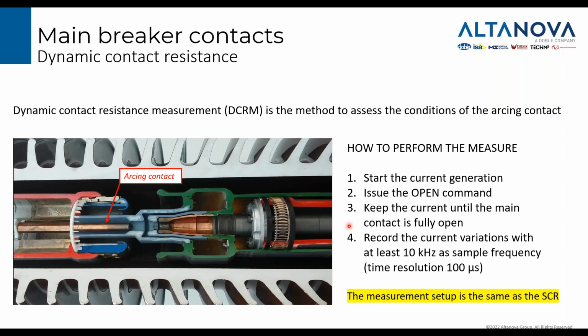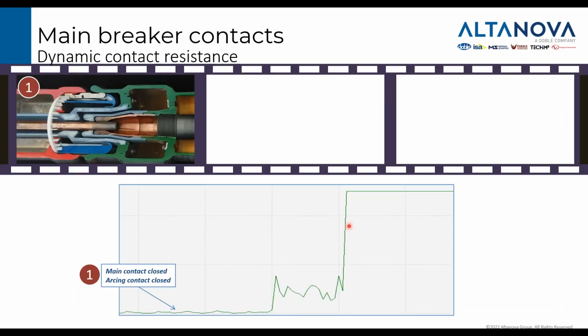We have to remember that all this happens in a few milliseconds, so you cannot measure all the signals with low sample frequencies. And the setup in terms of wirings for this measurement is exactly the same as for the static resistance. So all the considerations that we discussed for the static contact resistance apply to the dynamic resistance.